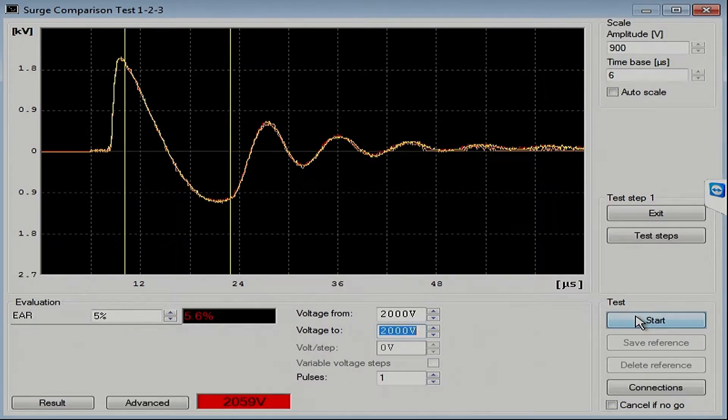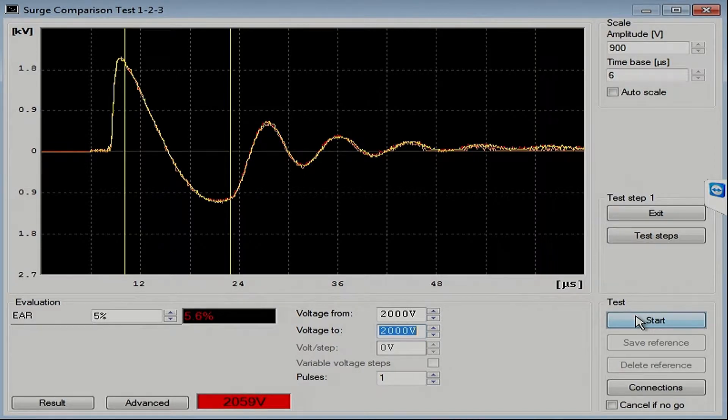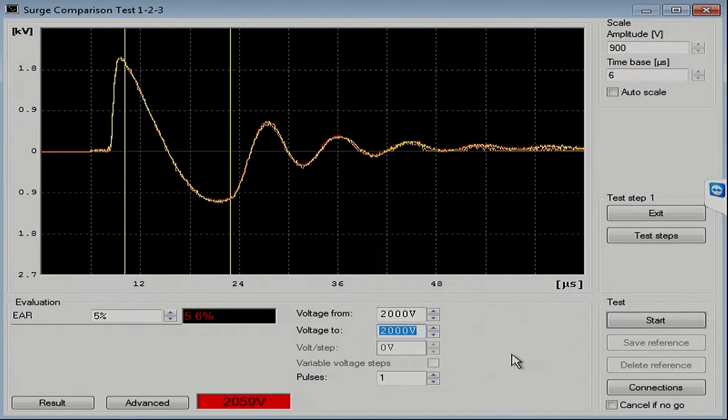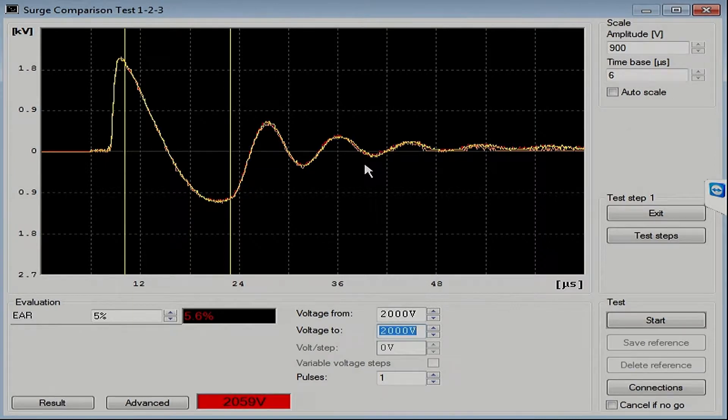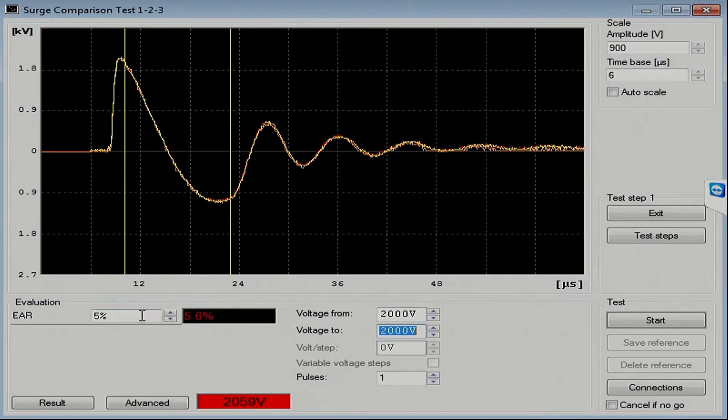There we go. There's three waveforms that you see there, and they're all on top of each other, which is what we would have expected. Now, in this case, since it is a random wound motor, there is a slight difference in the waveforms, and you can see them with your eye here. So, our five percent may not be such a good number here.